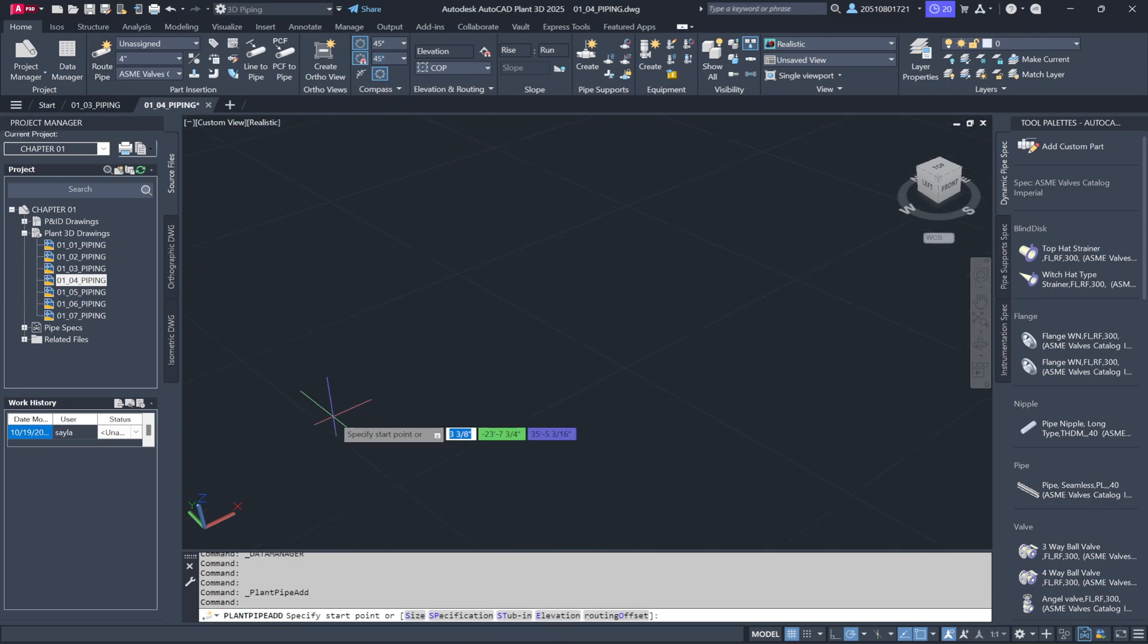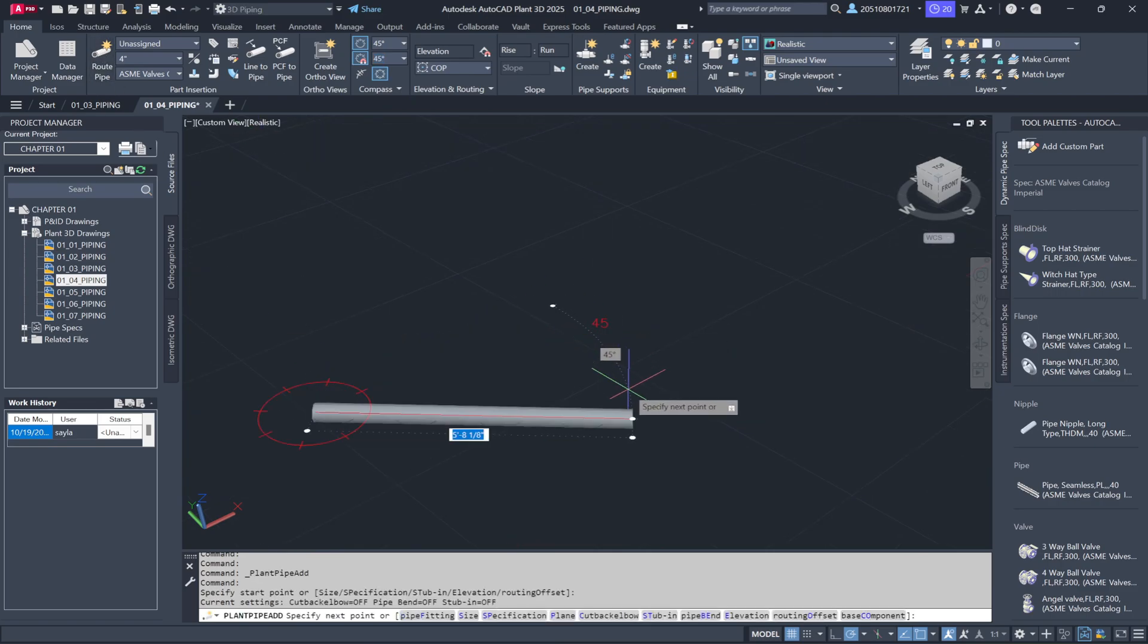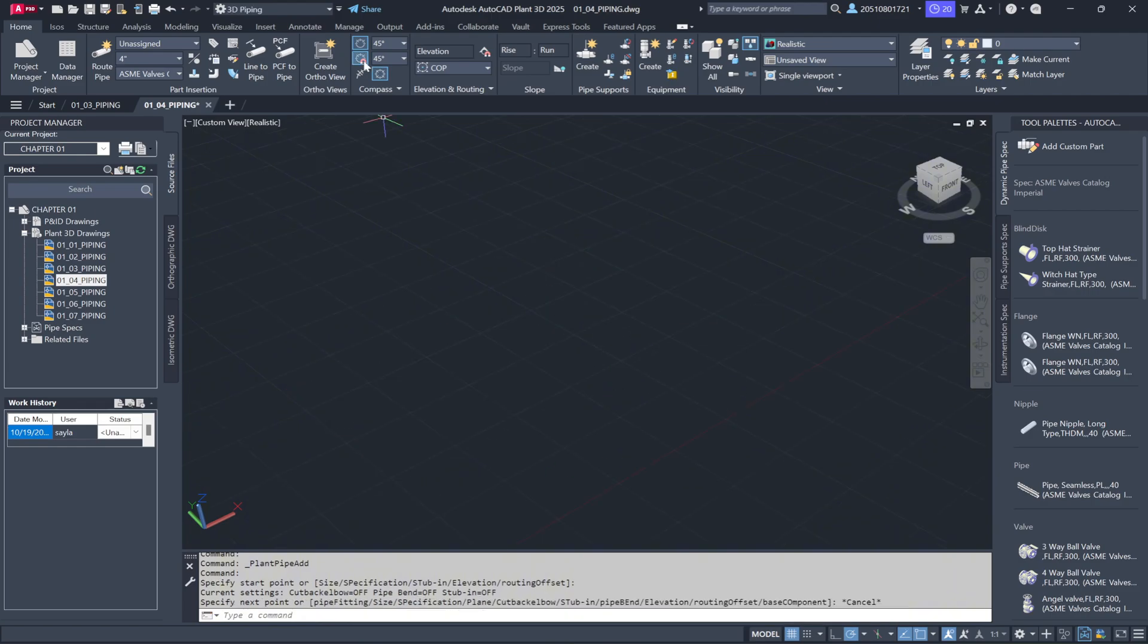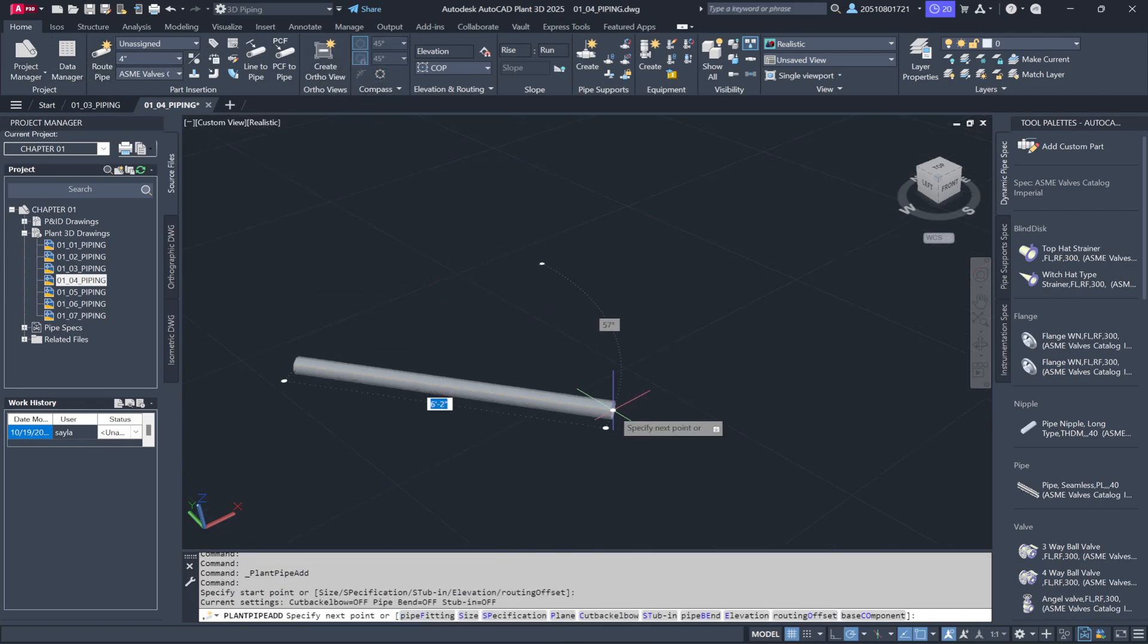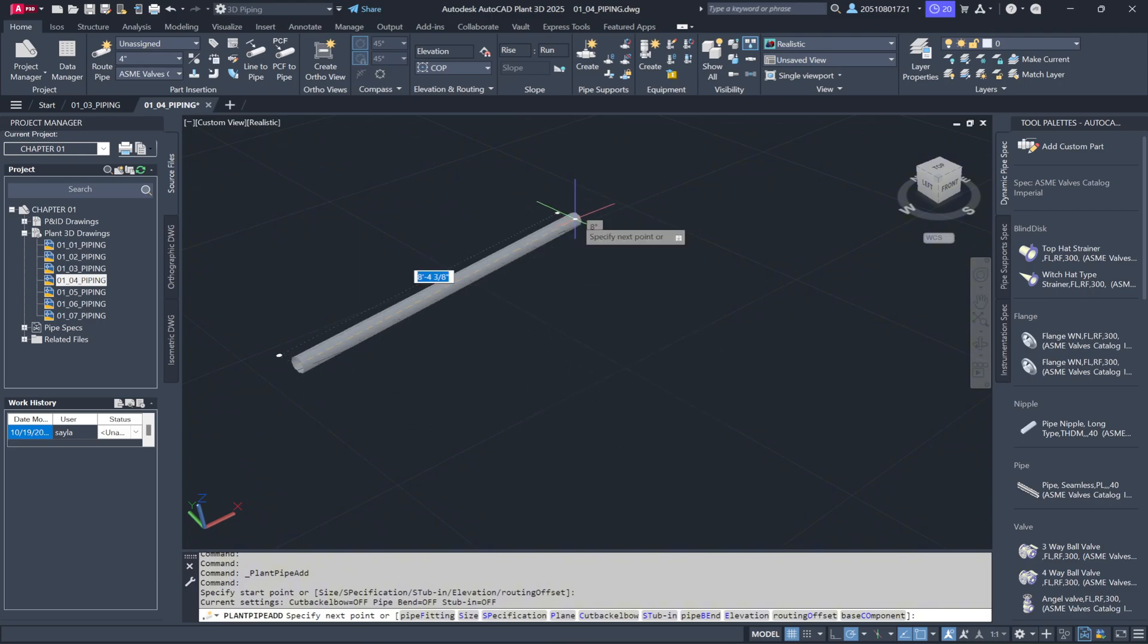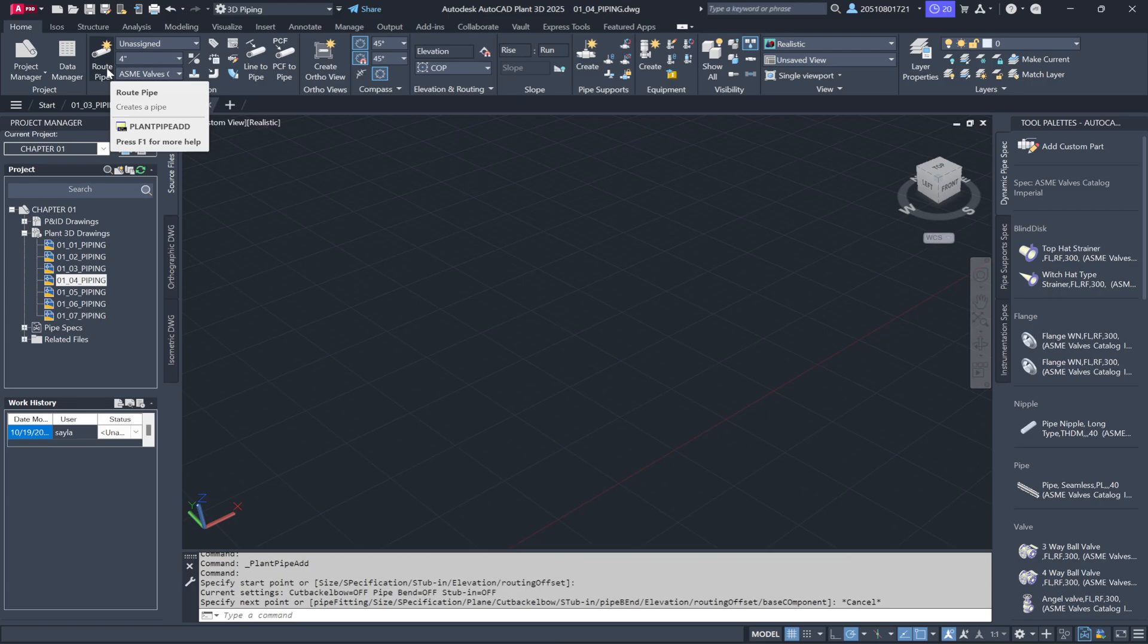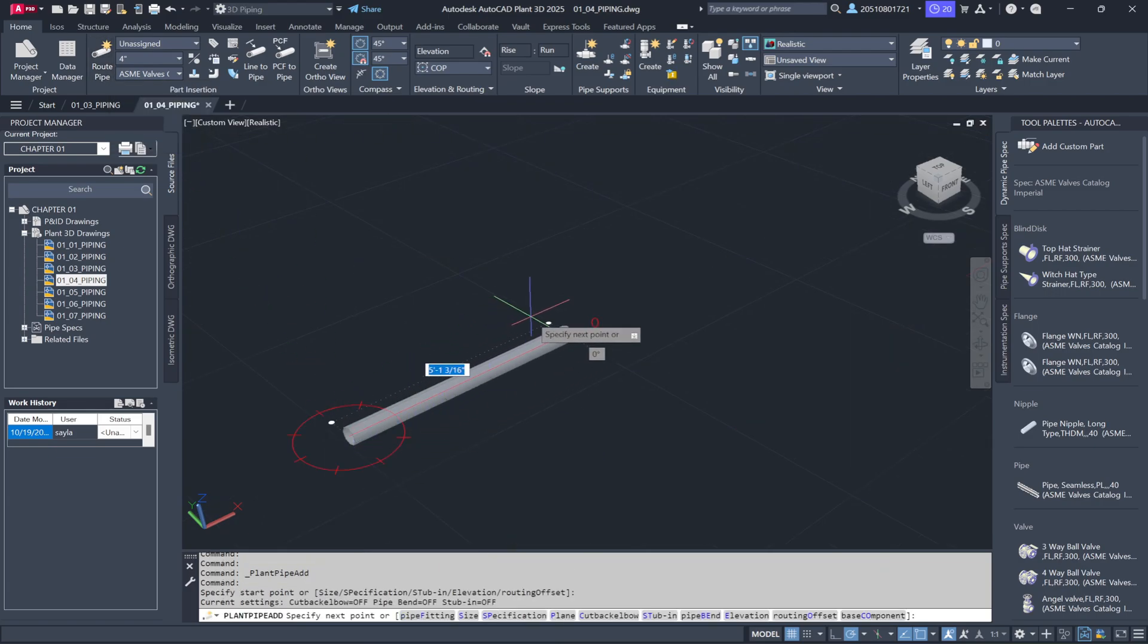Let me demonstrate. When you start a piping run, you'll see a red compass guiding the direction at set angles. You can customize these angles, turning off the snaps if needed, and specify custom angles as required. The Compass Tool can be toggled off if you prefer to run pipe without snap points. If you want to switch the compass to vertical or change directions, simply use CTRL right-click.